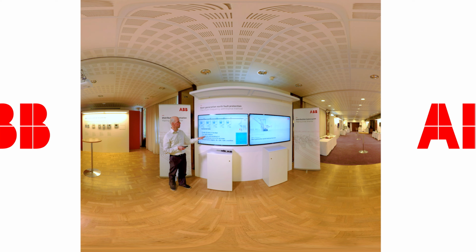In 2 days we conducted 52 different types of earth faults in 2 locations in these compensated networks. We varied the type of fault from continuous fault to restriking earth fault, which is a very typical fault in cable sections of the lines in the network.